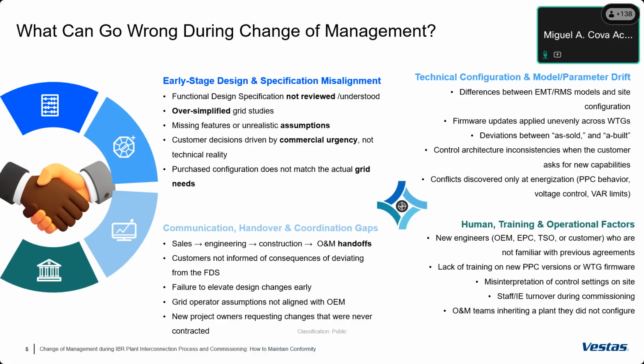Something that's often very difficult to capture is the conflict during energization. We are seeing this more and more. We had a couple of projects in Canada, for example, on a relatively strong grid 10 years ago. From phase 1 to phase 2, there were at least 6 to 8 other IBR plants connecting to the same site. The same customer decided to copy and paste the settings from the previous phase because everything was great, and then the voltage started flashing like a Christmas tree, because it was a relatively big wind farm. So it's very important that we discover these control interactions.